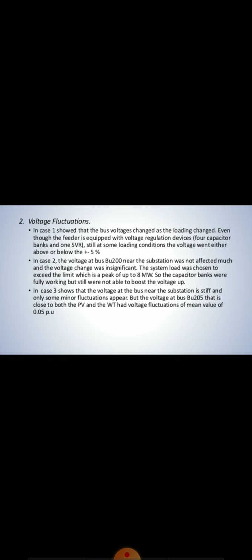Similarly, in case 3, the voltage of the bus near the substation is stiff and only some minor fluctuations appear, but the voltage at bus BU 205, that is close to both PV and WT, has voltage fluctuations of mean value of 0.05 pu.